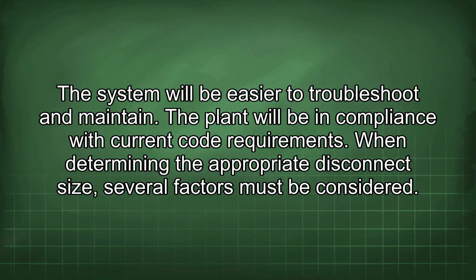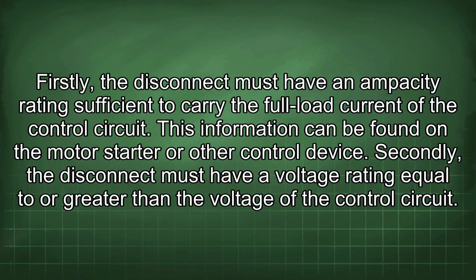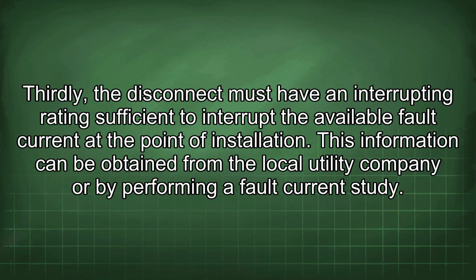When determining the appropriate disconnect size, several factors must be considered. Firstly, the disconnect must have an ampacity rating sufficient to carry the full load current of the control circuit. This information can be found on the motor starter or other control device. Secondly, the disconnect must have a voltage rating equal to or greater than the voltage of the control circuit. Thirdly, the disconnect must have an interrupting rating sufficient to interrupt the available fault current at the point of installation. This information can be obtained from the local utility company or by performing a fault current study.